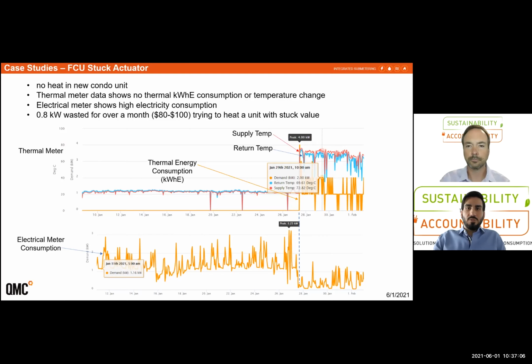As you can note from the supply and return temperature in red and blue, from the beginning of January till the 27th, when the service tech was dispatched to site, both temperature sensors are measuring near ambient temperature, around 20 degrees C within the suite, with near 0 delta T as the control valve or the actuator is stuck in the closed position, and the fan within the fan coil is operating constantly using electricity without the ability to satisfy the set temperature on the thermostat. As soon as the control valve and the actuator get serviced on the 27th, the supply and return temperatures go back to normal, near 70 degrees C, and the electricity consumption drops as the fan within the fan coil goes back to normal operation. Next slide, please.